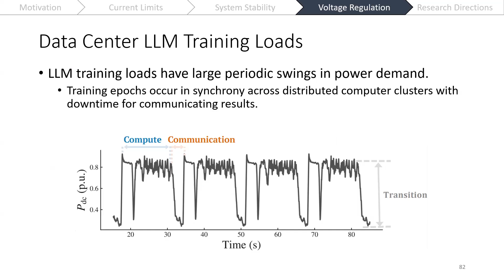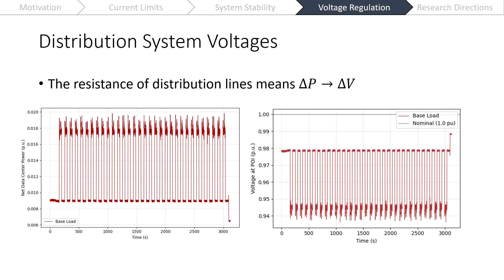If we look at how this impacts the voltages throughout our distribution system, even just the voltage here at the bus that the data center is connected to, since our lines have significant resistance in the distribution system, it shows that when we have these large steps in active power, we're going to see similar steps in the voltage of our system, proportionate to the resistance of the lines in our system. Here, dipping us well below our plus or minus 5% that we'd want to achieve.